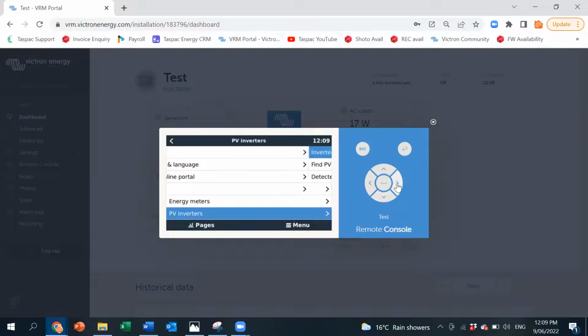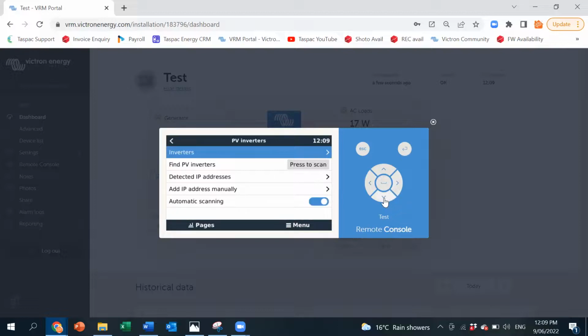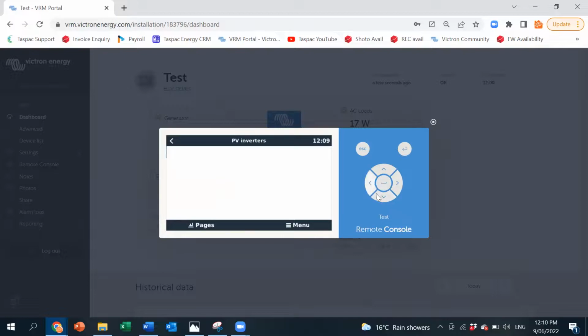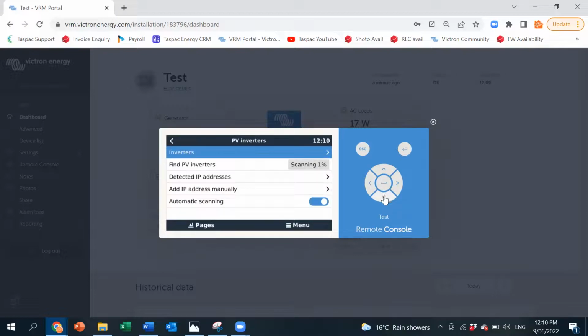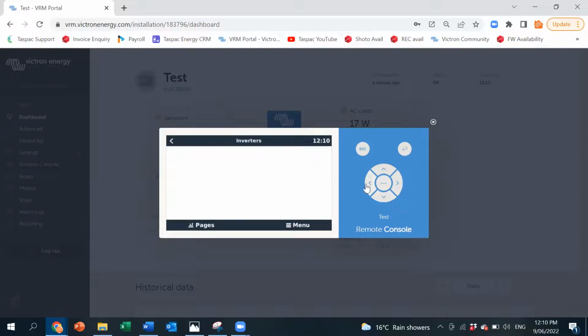PV inverters, so if we've got, say, a Fronius PV inverter attached to the same system on the same network, we would then scan that network. It will go through and try and find any PV inverters, and those PV inverters will then show up in the list, and you can then assign them where they are physically. Are they on the AC input? Are they on the AC output? Line 1, line 2, line 3, if you've got a 3-phase system. It will take some time to scan, so you could come back to that if you want to. Wireless AC sensors not used. Modbus TCP devices not used.